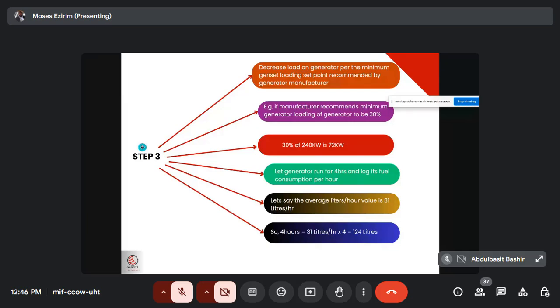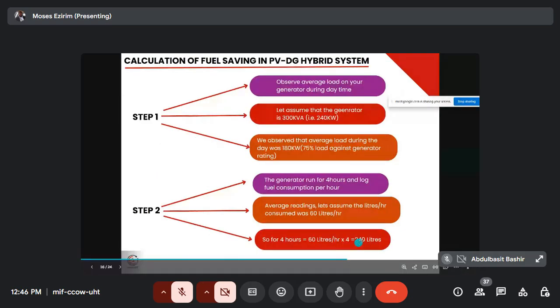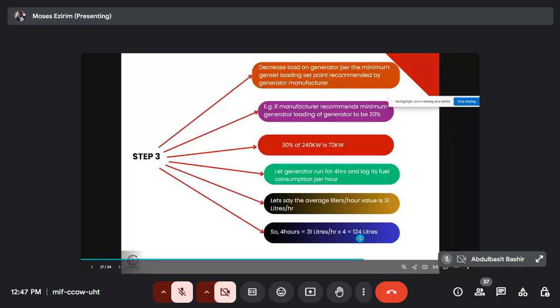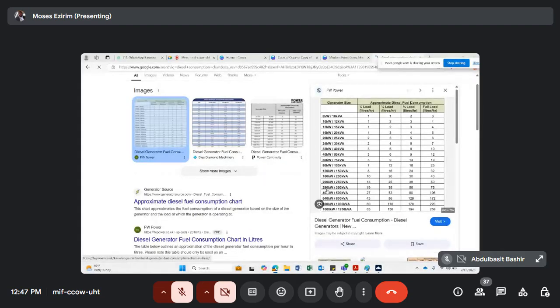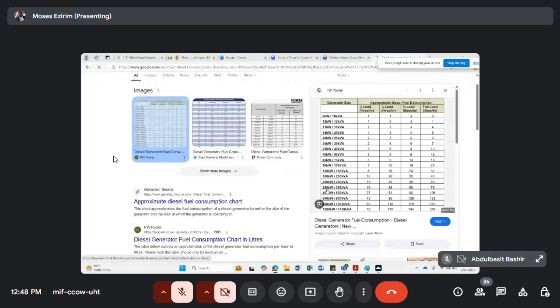Running at 72, consumption is 31 liters. So for 31 liters per hour, you can see what the consumption is. So instead of using 240 liters, can you see the screen? All right, so now you can see it has opened. Can you see it now? Let's go to this. Okay, this is it. Now if you run it at this load, you can see 29 liters per hour. Total savings, you can see 160 liters saved.